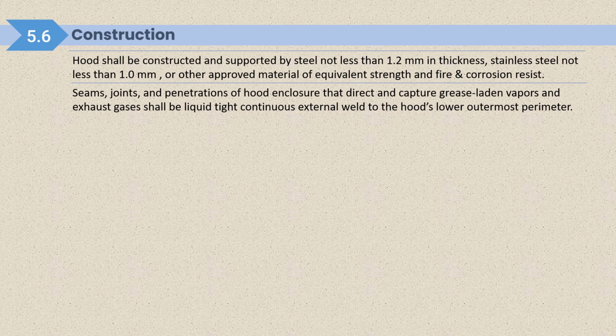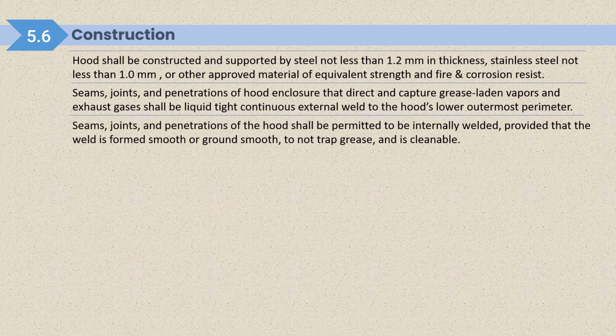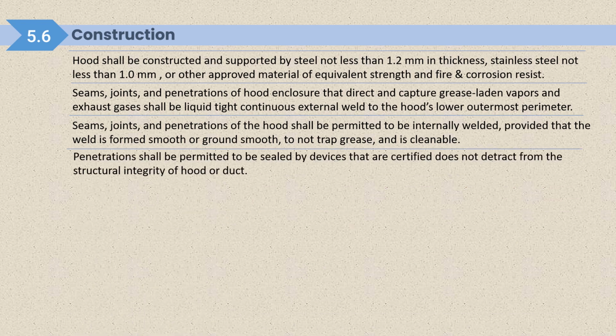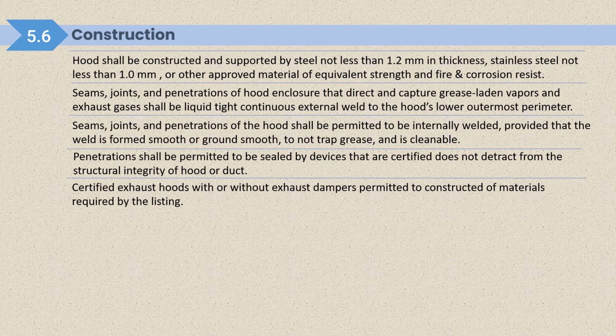Continuous external weld to the hood's lower outermost perimeter. So external weld is recommended here. Seams, joints and penetrations of the hood shall be permitted to be internally welded, provided that the weld is formed smooth or ground smooth to not trap grease and is cleanable. Penetrations shall be permitted to be sealed by devices that are certified and do not detract from the structural integrity of the hood or duct. So whatever material we are using to seal the penetration should not detract from the structural integrity of the hood or duct.